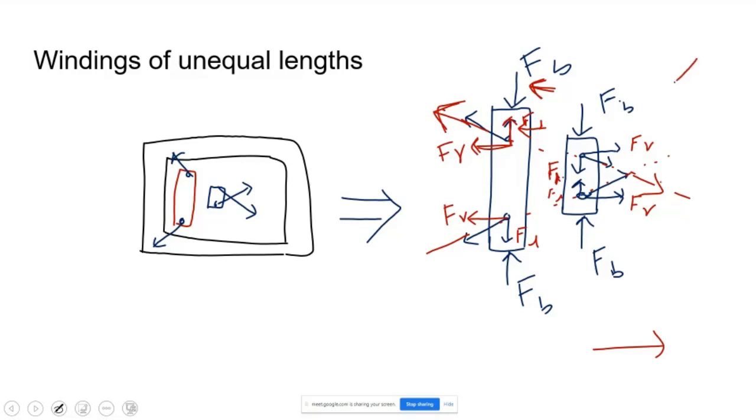And on the secondary, if you observe, it is exactly the reverse. Right? Yes, sir. The opposite. So it is trying to do this kind of thing. Under extremely high currents, the shorter winding tries to crush longitudinally, and the longer winding tries to burst longitudinally. So this is the interesting feature that you have to understand.